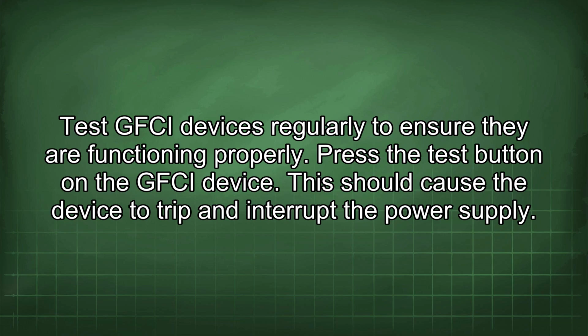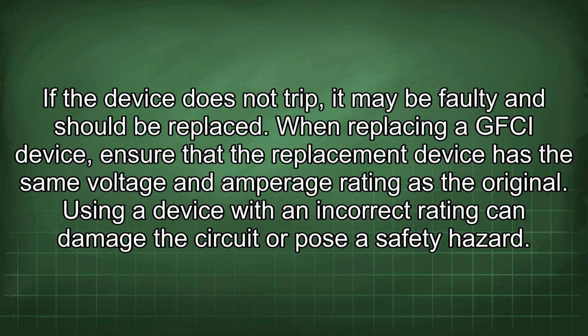Press the test button on the GFCI device. This should cause the device to trip and interrupt the power supply. If the device does not trip, it may be faulty and should be replaced.